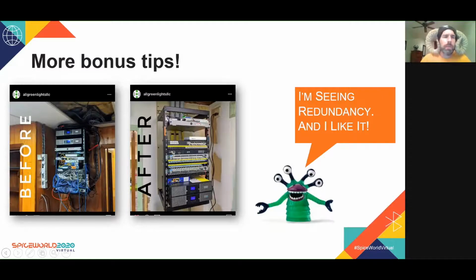The photo on the left shows the before, with the UPS at the top of the rack. They've smartly moved that to the bottom in the after. It's also a redundant solution, with two UPSs both supporting the same load, plus an automatic transfer switch in the middle of the rack, which is a great best practice to include. That redundant solution is really the most reliable, so it's always good to see that. That's another good bonus tip for you.